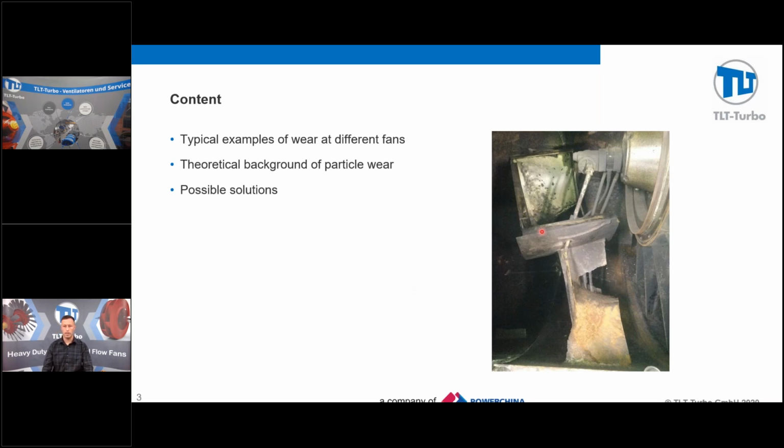And for an example on the right, as we talked about for multi-scenarios, which is why we're going to do the multi-session webinar on this, you can see that this fan, the rear nacelle portion covering the hydraulic unit, the actual stator vanes completely broke off. The actual whole nacelle section collapsed in the fan itself, and this was due to they picked up a high particle count in the fan system at prolonged mining.